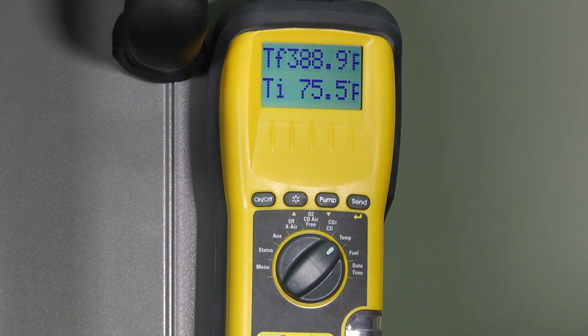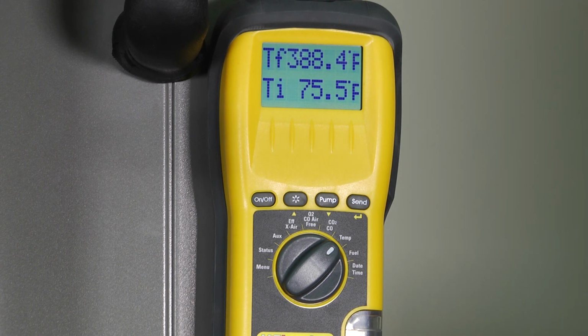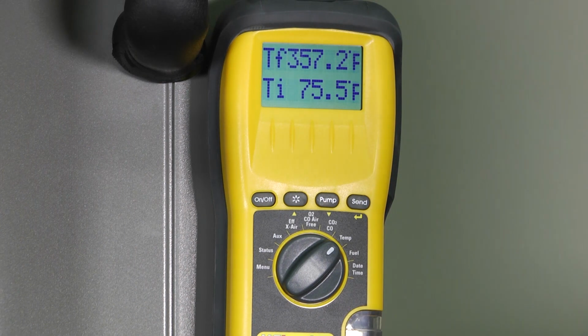So if the first thing I do on my maintenance is check my gas pressure, and my gas pressure is fine, but my temperature is really high, I'm going to start to question whether I've got carbon inside my heat exchanger that's not letting the heat transfer across the system itself. Now, in this particular case, my furnace has reached the temperature I want it to be. I know my heat exchanger is good, and I know my gas pressure is set right because my temperature is where I want it to be.